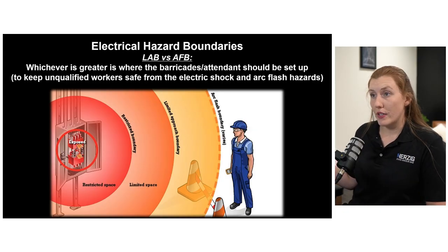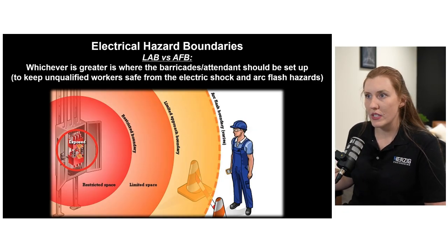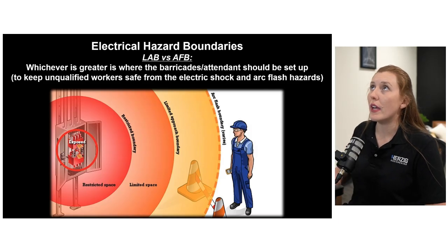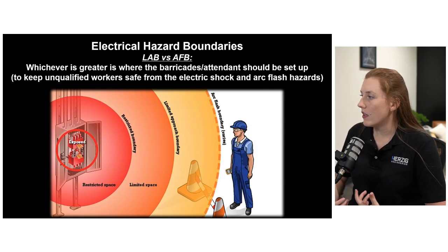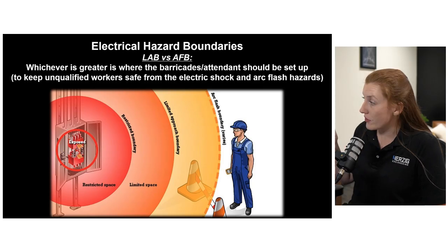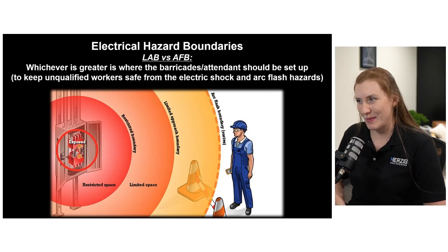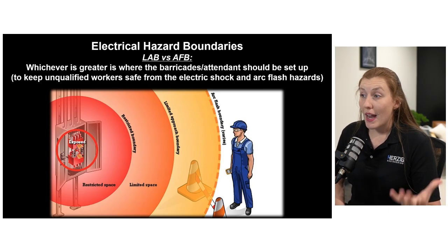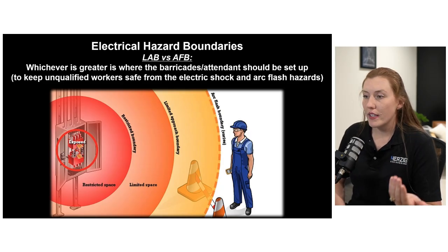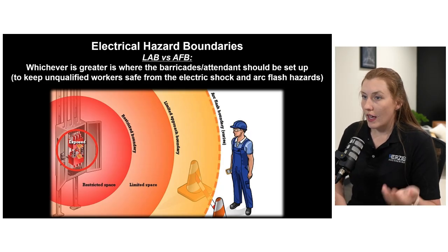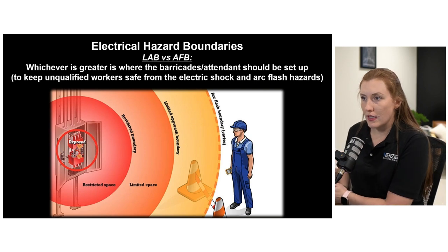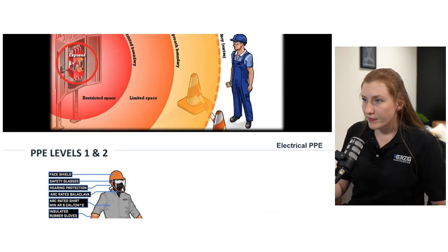Then the arc flash boundary - that's not the point where people are safe. It's calculated to 1.2 calories per centimeter squared. They could still walk away with a second-degree burn if they're standing right at the boundary, like so many people do. So I say bump it out another couple feet, protect people from second-degree burns as well. Again, bare minimum versus best practice is something to consider.